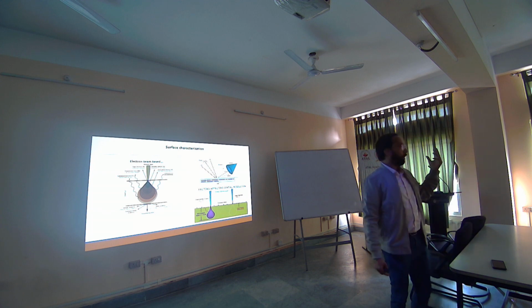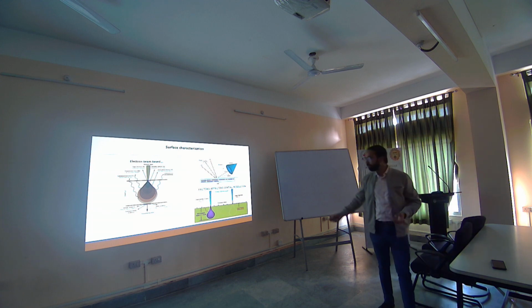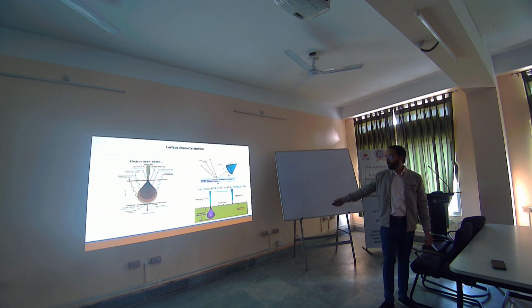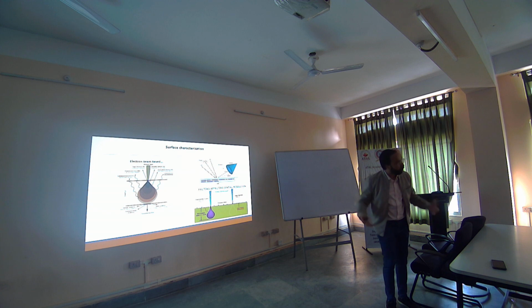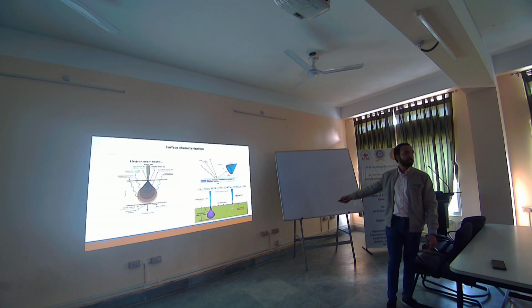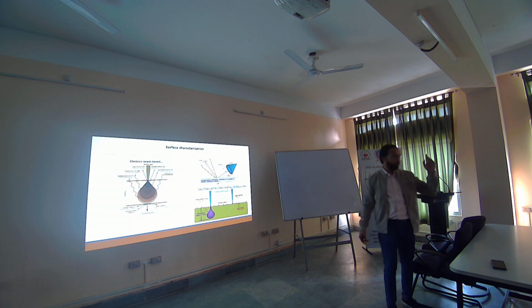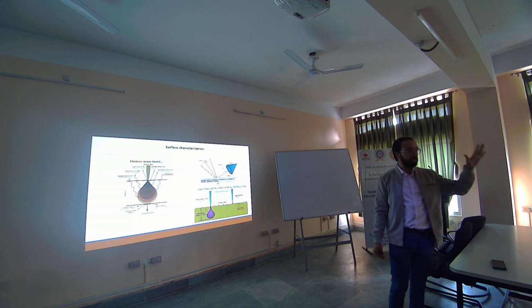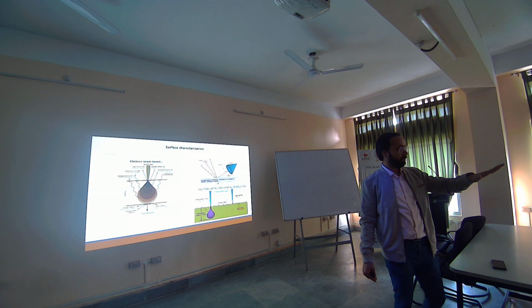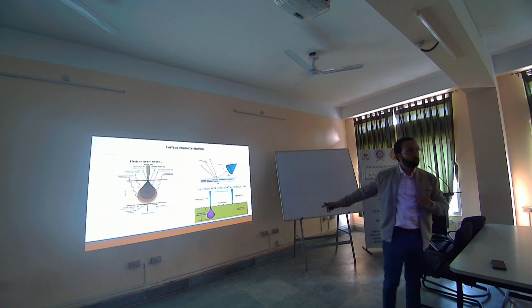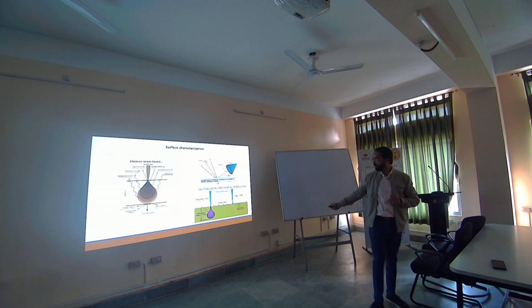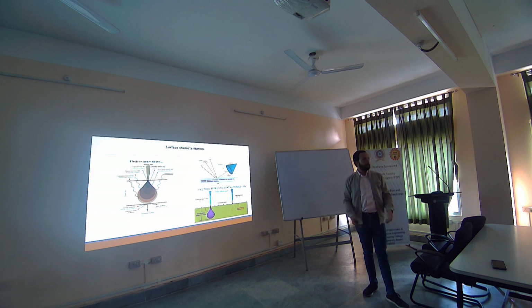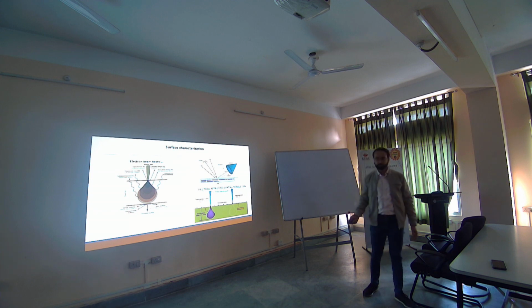So your EDX, that means when you are using the same electron beam, but you are measuring the X-ray response, you can measure to a depth of 1000 times that you can measure with AES. That is what I told you, the difference between using AES and EDX. Remember that, right? That is the difference. AES is surface sensitive, EDX is depth or volume sensitive. Okay.